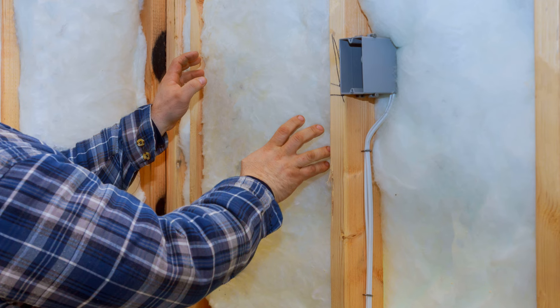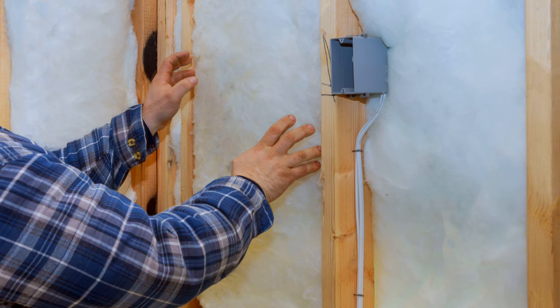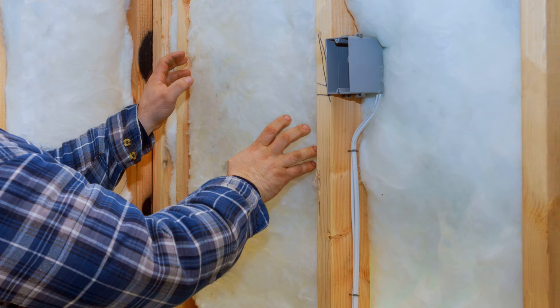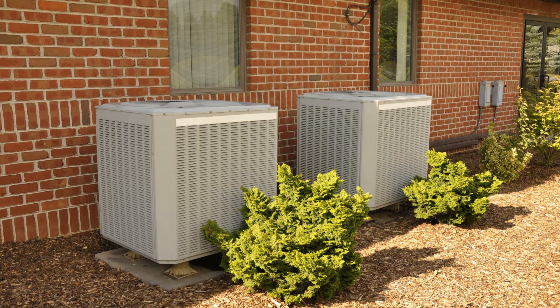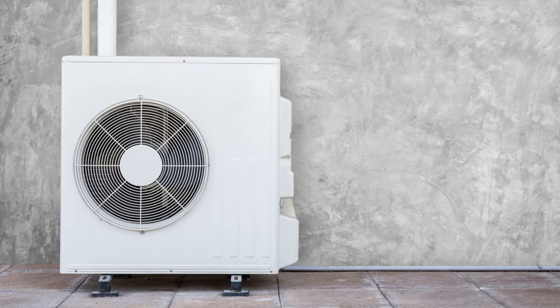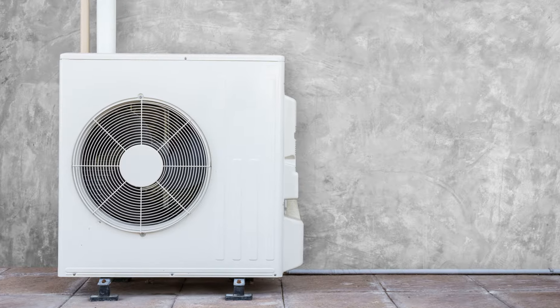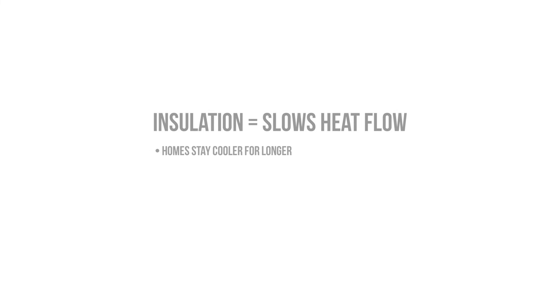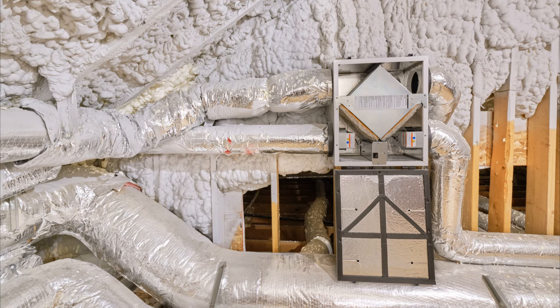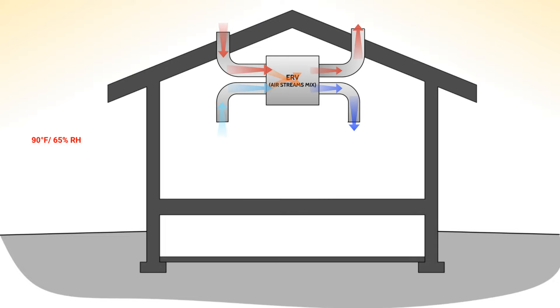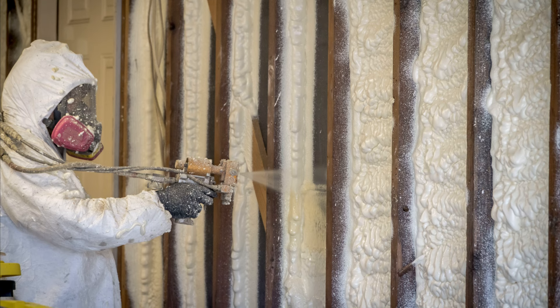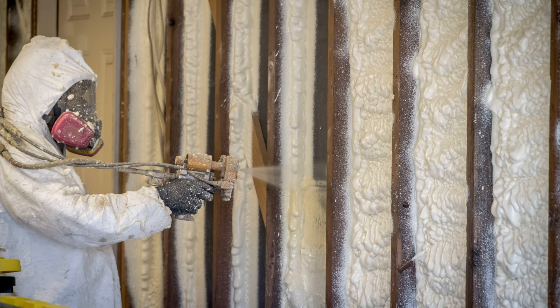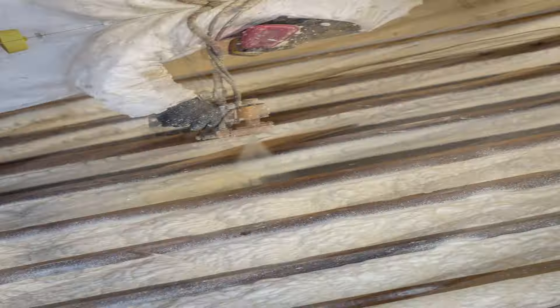We also have to contend with the fact that when we go to insulate, any incidental dehumidification benefits provided by the air conditioning system are essentially eliminated since we've reduced the loads on the air conditioning system, as that cool conditioned air stays in the home for longer, increasing relative humidity levels unless a dedicated dehumidifier is provided. Overventilating with fresh air systems like ERVs can also dump a bunch of moisture from the outside into the home and raise relative humidity if we aren't careful.